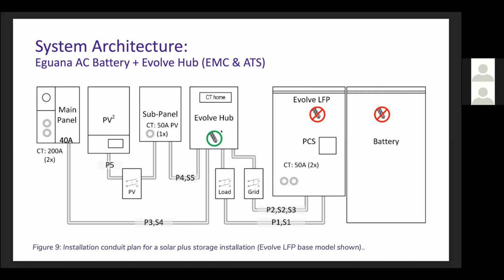But because of the new NEC and the PCS controls through the Evolve Hub, that's a nice added benefit. So keep that in mind. Also keep in mind that if you are using that exact setup, SolarEdge 7600, you've got to have a way of curtailing that when you go to off-grid mode, because that battery inverter is only a 5 kW inverter, it will only charge up to 5 kW of excess PV. So that SolarEdge 7600 has got to be derated down to 5 kW or maybe 5,700 watts nameplate rating, and that can be done through controls and a relay interface that we've got on our PCS, and then through the PRI, the power reduction interface on the SolarEdge inverter.